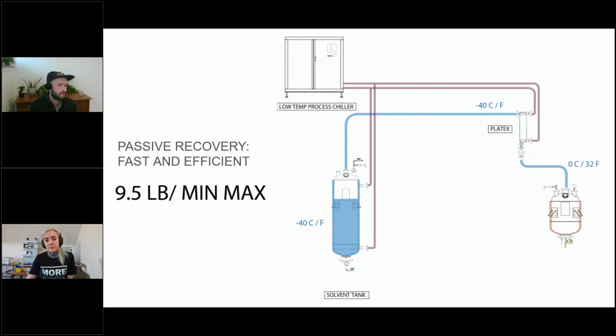Yeah, anything on passive recovery? Oh, the other thing that's really nice about passive recovery is recovery pumps are dangerous. They can generate 400 psi at their outlet really easily. It's enough to do some significant damage. With passive recovery systems, all of your pressure that gets created gets condensed, so you don't have anything that can create any pressure really. Obviously you can shut the valve on your recovery pot and that'll climb up to 60 psi or something like that. But for the most part, passive recovery systems operate at 5 or 10, and that's pretty safe. That's a lot less than a bike tire.